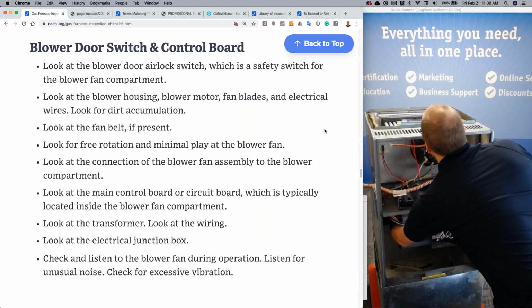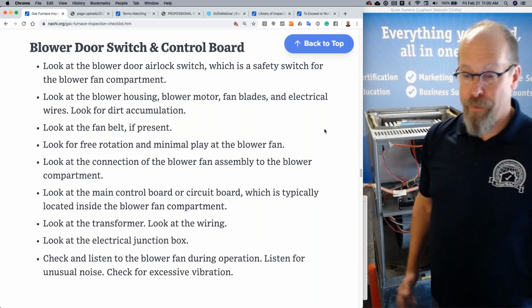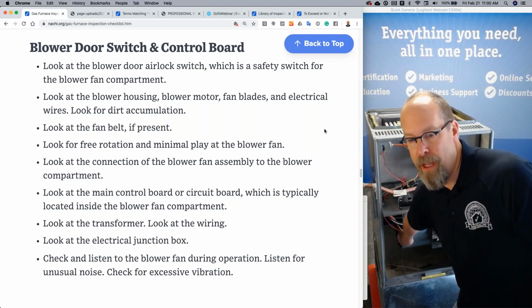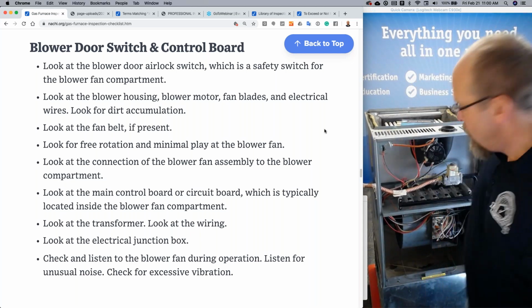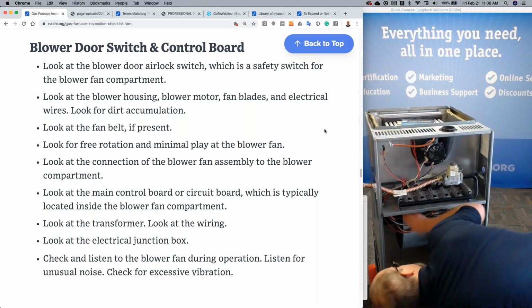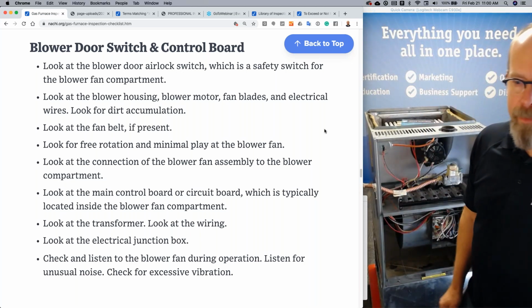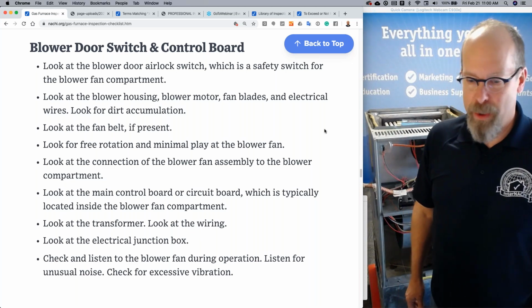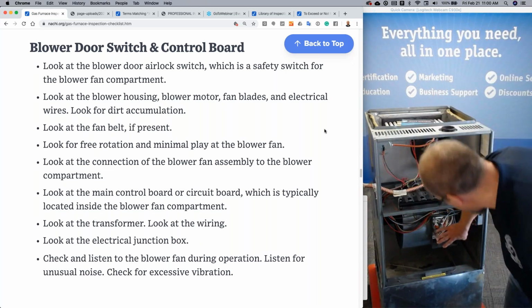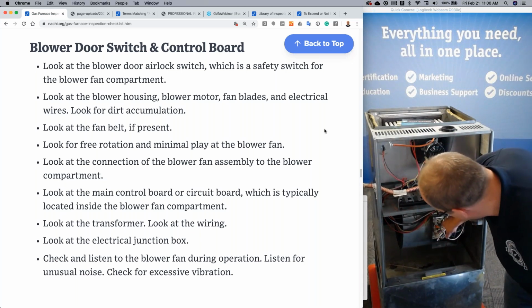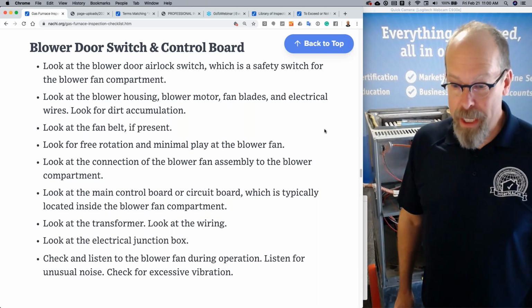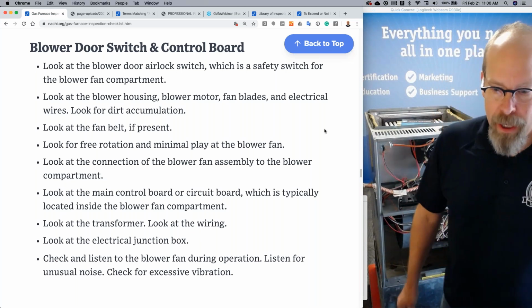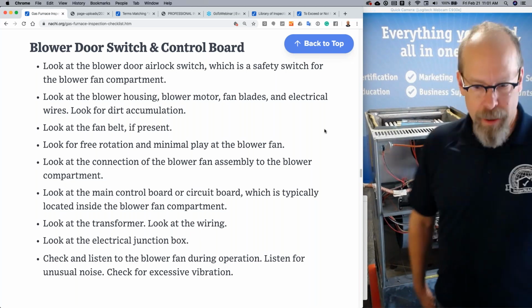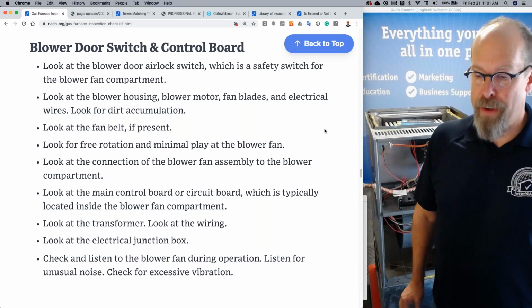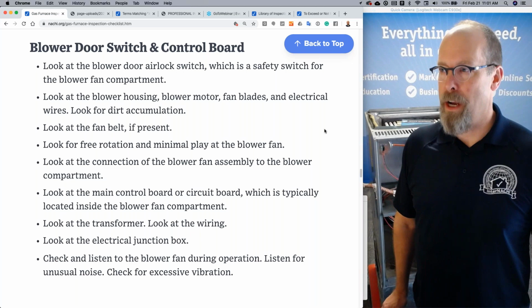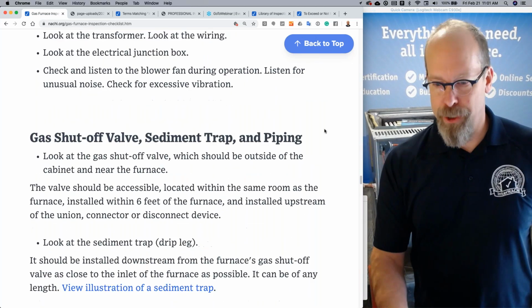And the blower fan is there. There's no belt. Look for free rotation, minimum play of the blower fan. Look at the connection of the blower fan assembly to the blower compartment, right? It's usually hung at the top. Look at the main control board, the circuit board, which is typically located inside the blower fan compartment right there. Yep. And remember those error code light bulbs are right there. Look at the transformer, look at the wiring, looks good. Look at the electrical junction box, got it. Look, check and listen for the blower fan during operation. Look for and listen for unusual noise or excessive vibration.